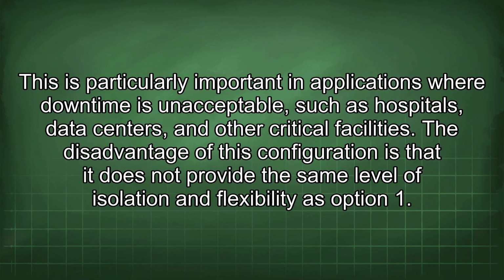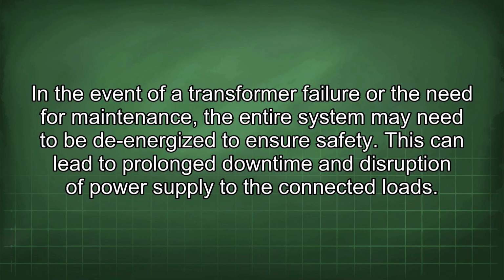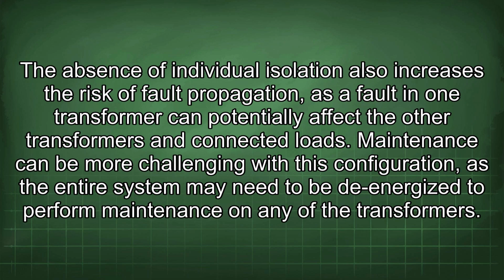The disadvantage of this configuration is that it does not provide the same level of isolation and flexibility as Option 1. In the event of a transformer failure or the need for maintenance, the entire system may need to be de-energized to ensure safety. This can lead to prolonged downtime and disruption of power supply to the connected loads. The absence of individual isolation also increases the risk of fault propagation, as a fault in one transformer can potentially affect the other transformers and connected loads.